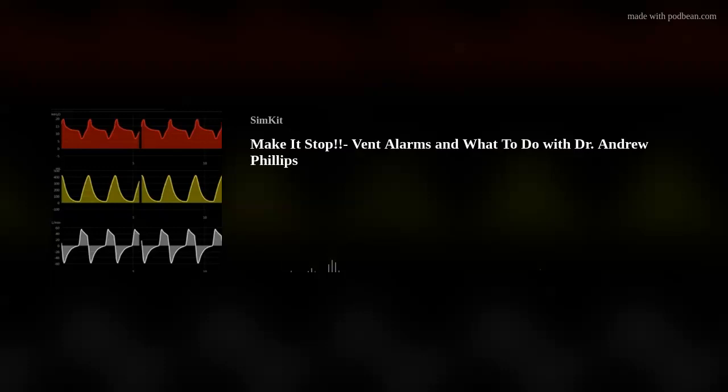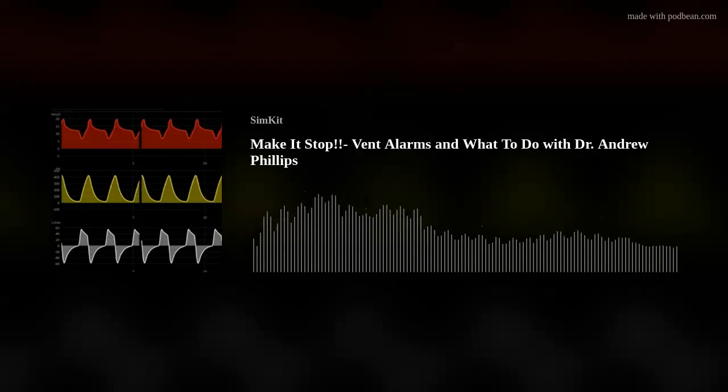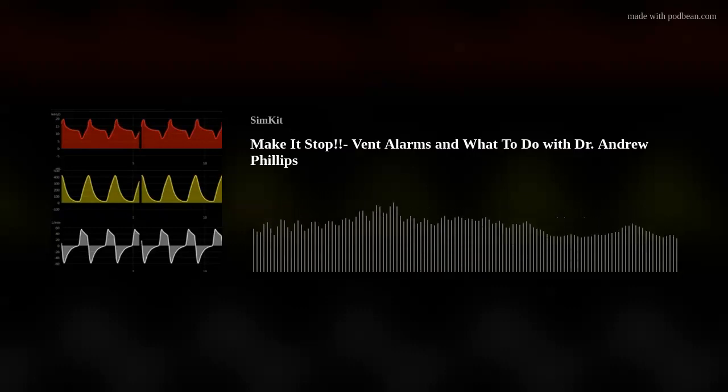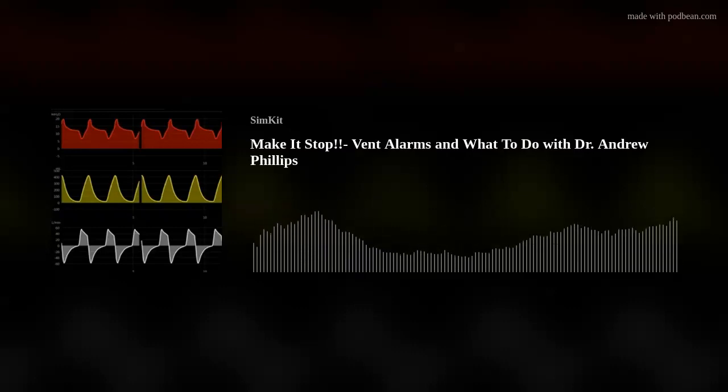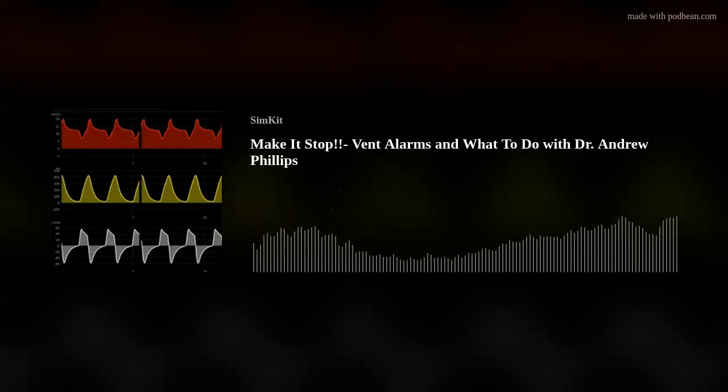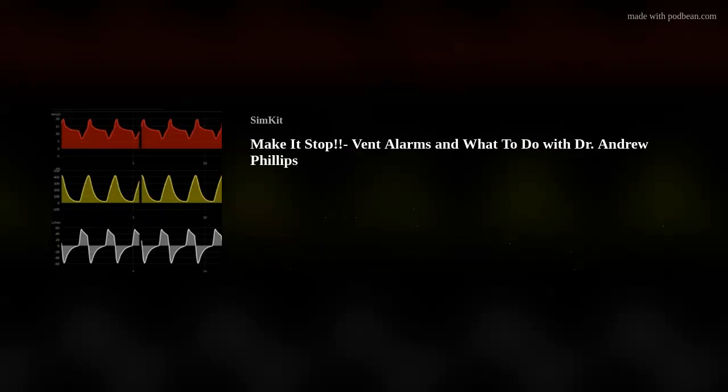So you're on shift, and you intubate a patient for an acute polypharmacy ingestion as a suicide attempt overdose. They have a suppressed GCS. You go high-five yourself in the mirror of the bathroom, say, man, I'm a good doc. I handled that airway great. You move on to the next patient. Nurse calls you 10 minutes later for vent alarms. You go in the room and you see a high respiratory rate alarm. Andrew, what's going on here? I set the respiratory rate at 18. Why is the machine saying that they're now breathing 30?